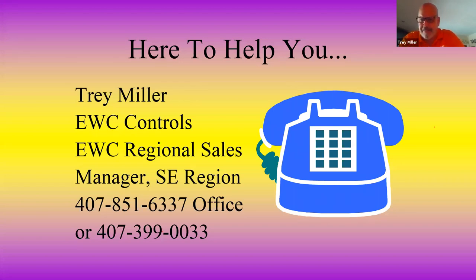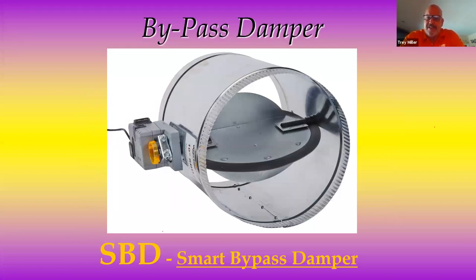First of all, the smart bypass damper. Guys, I tell you, working 13 years for a distributor, from a distributor standpoint, from a manufacturer's rep standpoint, this is a product that has changed everything. If you have guys who've done zoning in the past, and they're not happy with it or they don't think it works, the reason is because they were not maintaining airflow through the system at all times. ACCA will tell you the only way to make zoning work properly is to make sure the unit doesn't know it has zoning on it.